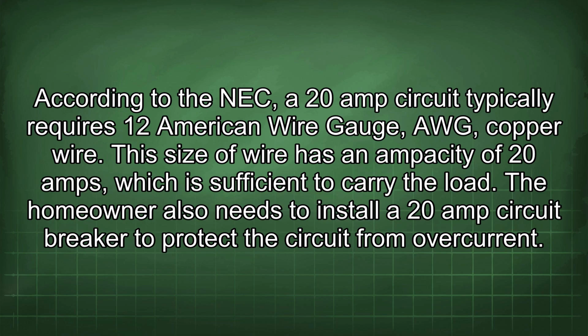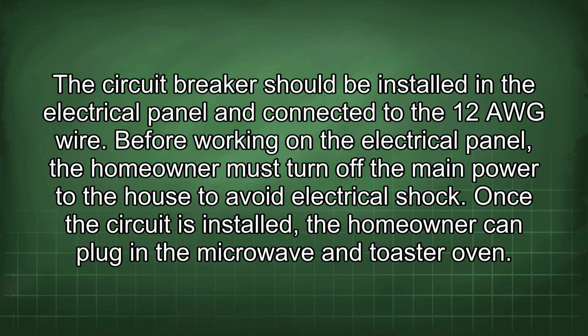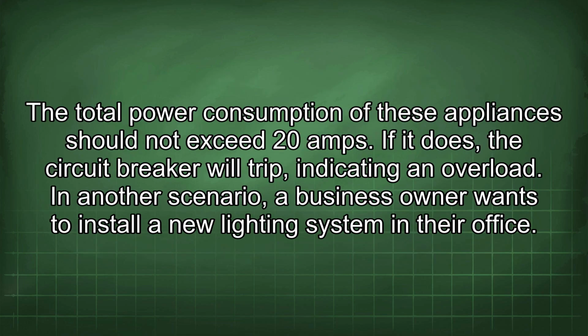The homeowner also needs to install a 20-amp circuit breaker to protect the circuit from overcurrent. The circuit breaker should be installed in the electrical panel and connected to the 12 AWG wire. Before working on the electrical panel, the homeowner must turn off the main power to the house to avoid electrical shock. Once the circuit is installed, the homeowner can plug in the microwave and toaster oven. The total power consumption of these appliances should not exceed 20 amps. If it does, the circuit breaker will trip, indicating an overload.